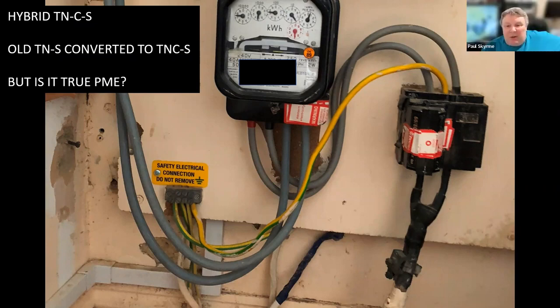To be honest, I would put it as a TNCS because it's a combined system. They're using the neutral as the earth conductor on the DNO side of the cable, and splitting it once it comes into the premises. So I'd put that down as TNCS personally. No, I agree. Your fault current behaviors would be based on TNCS or neutral loop path characteristics at that point.